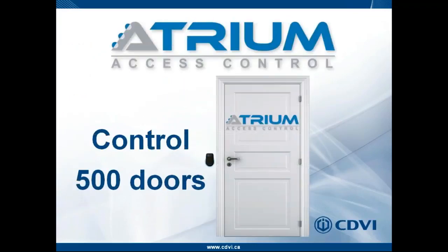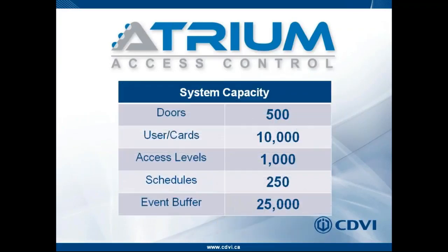The capacity of the system: Atrium, the original system which we released a little over 5 years ago, was limited to 10 doors. Over time, we've increased the capacity. As you see now, we are up to 500 doors with the Atrium solution. So the database, as we see: 500 doors, you can have 10,000 users, or what many people call cards in the card database, the user database. 1,000 access levels, so which doors at what time, so you can configure up to 1,000 different access levels.